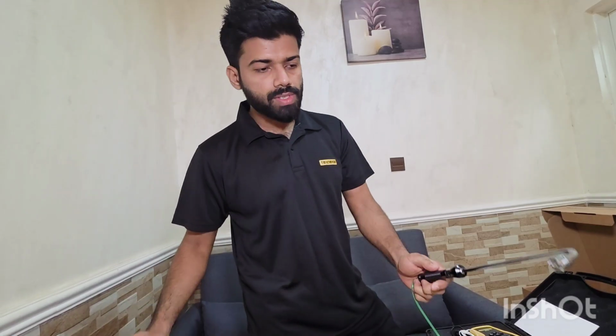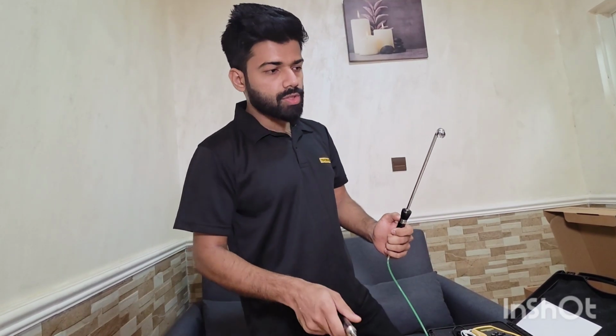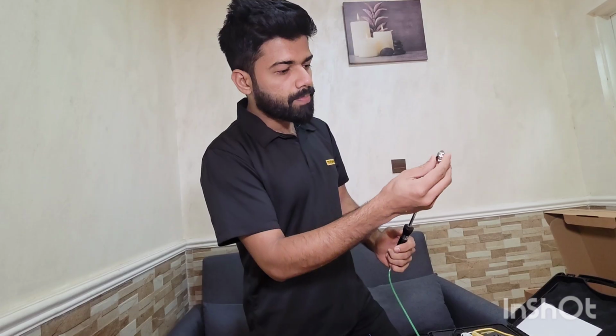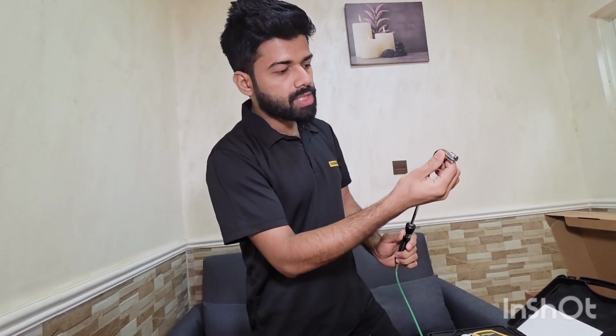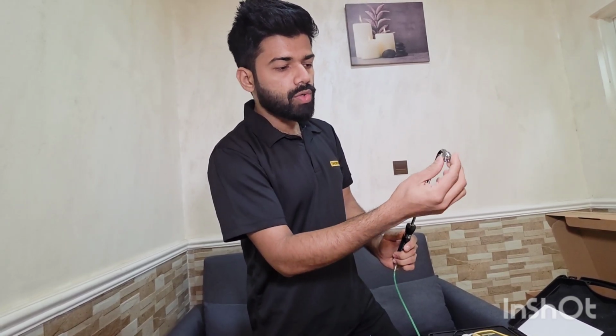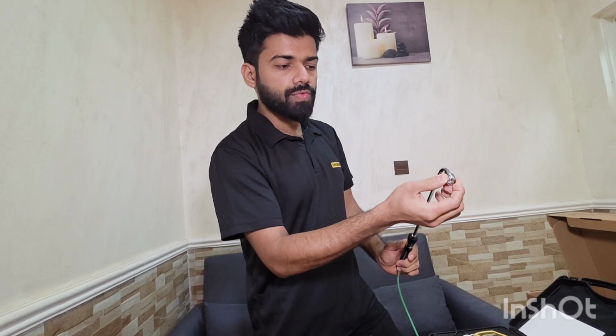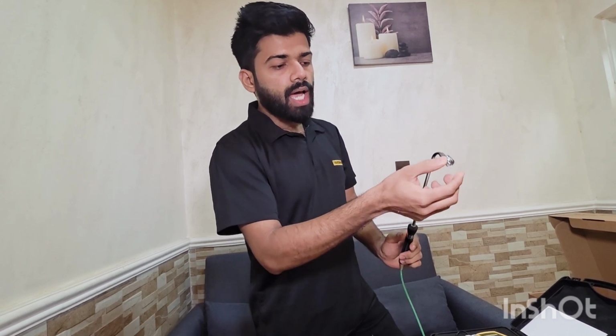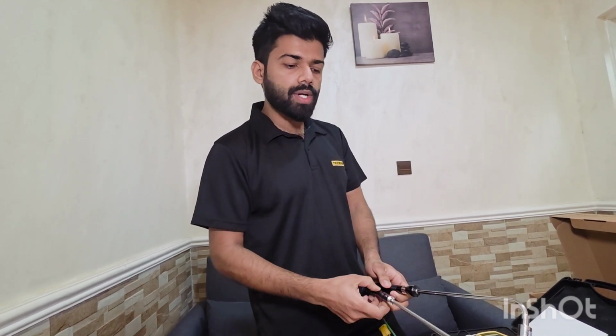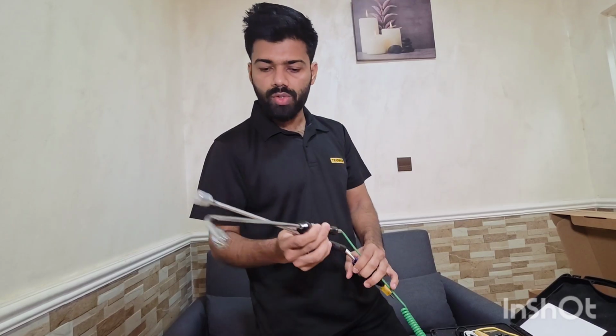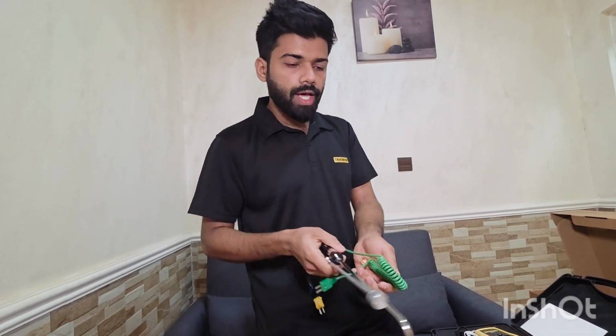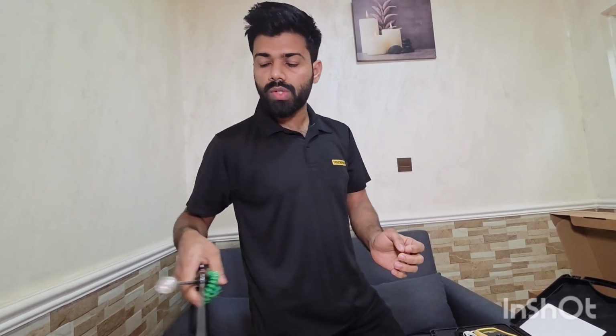And the surface probes are similar to that. This part and all can withstand up to 400 degrees Celsius only. So this is safe to use from -50 to 400 degrees Celsius only. And there is a high temperature probe, which is the TP980. I didn't take that here. It can measure from -50 to 1100 degrees Celsius. That probe comes in a rounded shape, and it can extend.